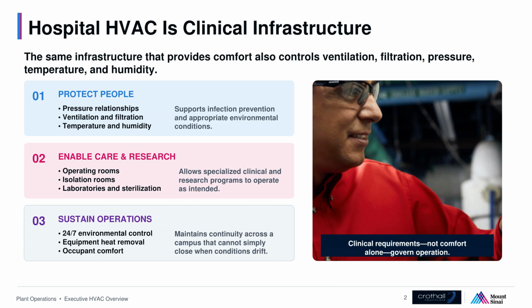Most people think of HVAC as heating and cooling. In a hospital, it is clinical infrastructure. The same systems that provide comfort also control ventilation, filtration, temperature, humidity, and pressure relationships. Those conditions help protect patients and staff, support operating rooms and isolation rooms, enable laboratories and sterile processing, and remove heat from equipment and data spaces. The operating requirement is therefore larger than comfort. A room can feel acceptable and still be outside its required airflow or pressure relationship. Our responsibility is to maintain the conditions that the approved design and clinical program require.